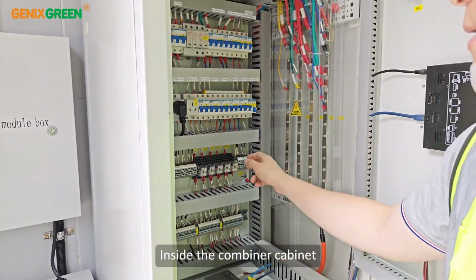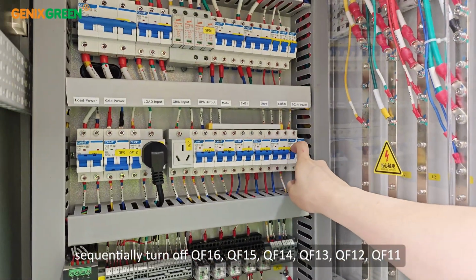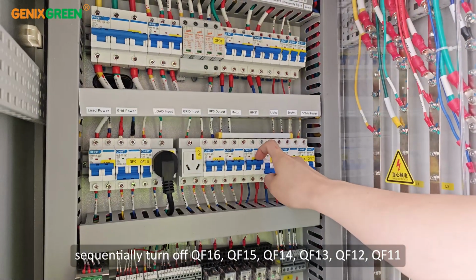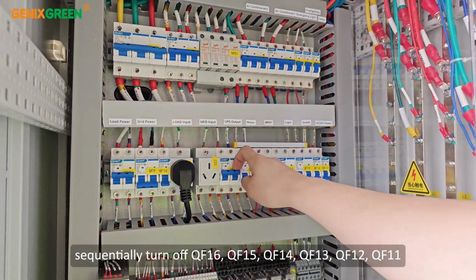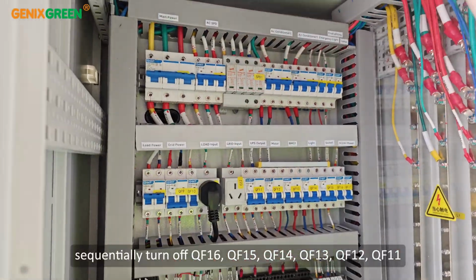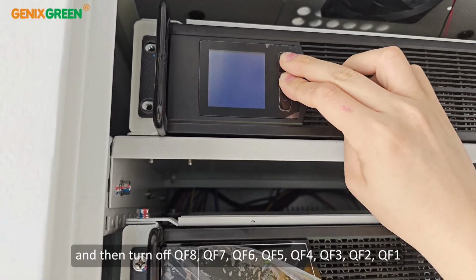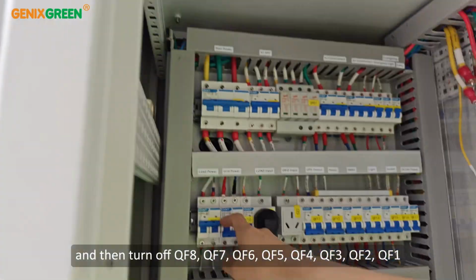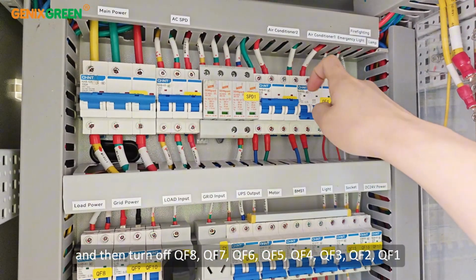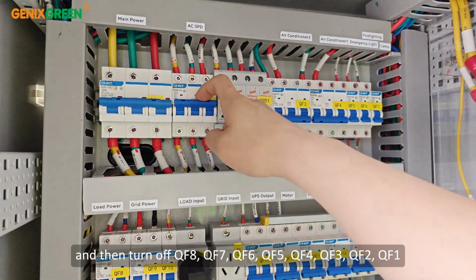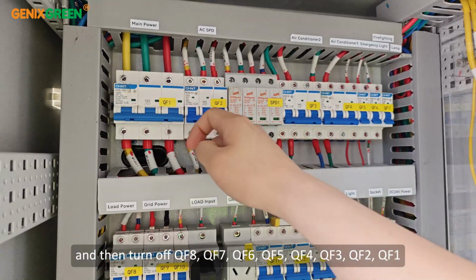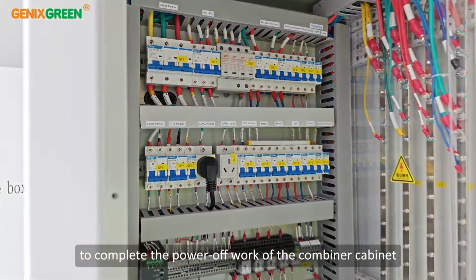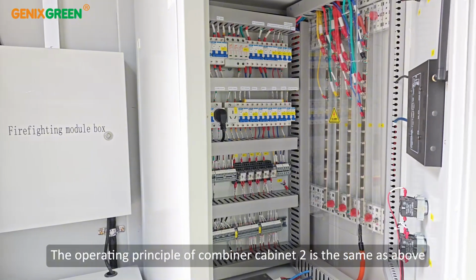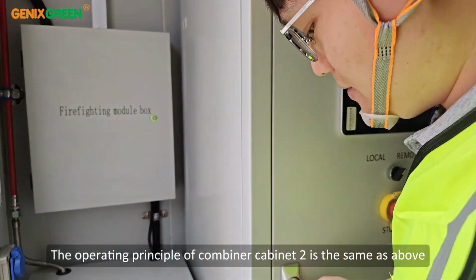Inside the combiner cabinet, sequentially turn off QF16, QF15, QF14, QF13, QF12, QF11, press and hold the UPS shutdown button, and then turn off QF8, QF7, QF6, QF5, QF4, QF3, QF2, QF1 to complete the power-off work of the combiner cabinet. The operating principle of combiner cabinet 2 is the same as above.